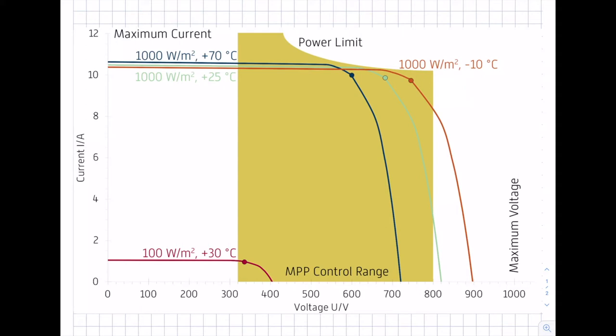The green curve represents the standard testing conditions: 1000 watts per square meter, a module temperature of 25 degrees Celsius, and an air mass of 1.5. You can see the slope of the curve with the maximum power point marked with a green spot.